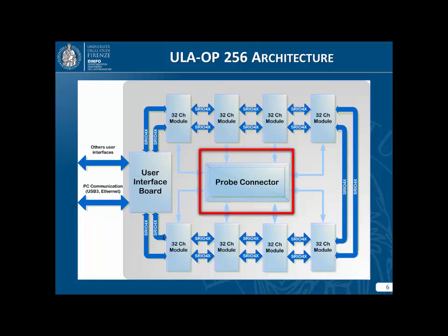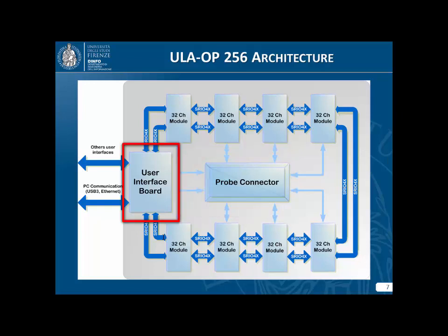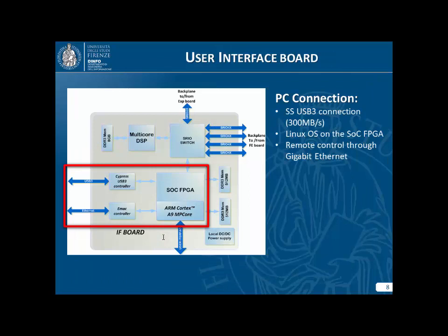And we studied, and we ended up with a solution for probe connection. On the back plane, we have another probe connector, which is easily replaceable, and we can interchange between different probe adapters. One special board is a user interface board, which manages the digital connection to the external world. And I start from this board.